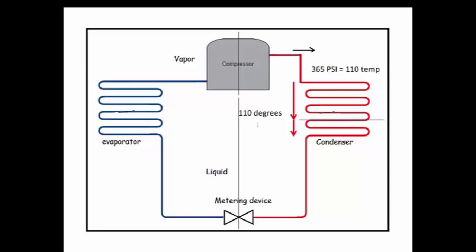Subcooling is a measurement of how much the liquid in the condenser cools down below its saturation point before exiting. When the hot gas in the condenser first turns to the liquid, its temperature is at its saturation point. This means that the temperature of the liquid is at the same temperature at which the refrigerant is condensing.